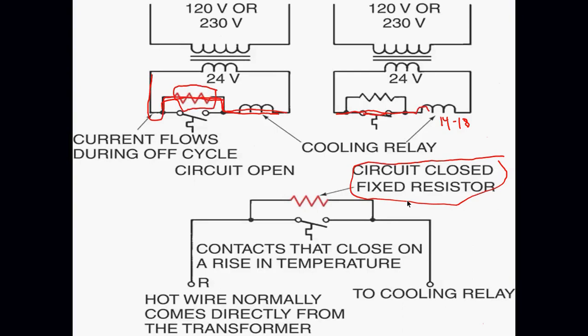Okay. Does anybody know what the difference between the cooling and the heating anticipator is? Okay. The heating anticipator is adjustable. The cooling anticipator is fixed. It's a fixed resistance. Okay. The heating anticipator is adjustable. That's your difference. Somewhere, someplace, you're going to be asked about it.